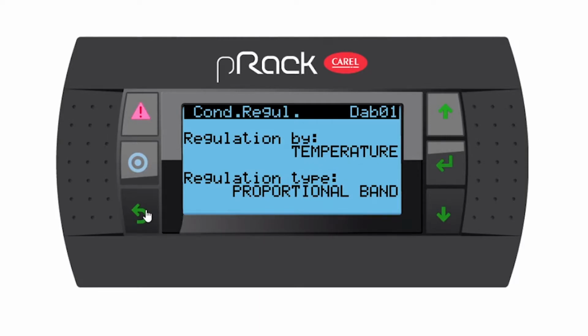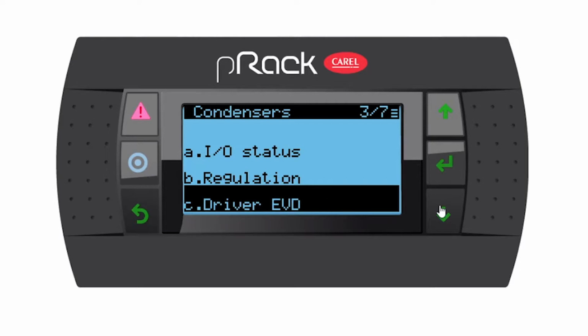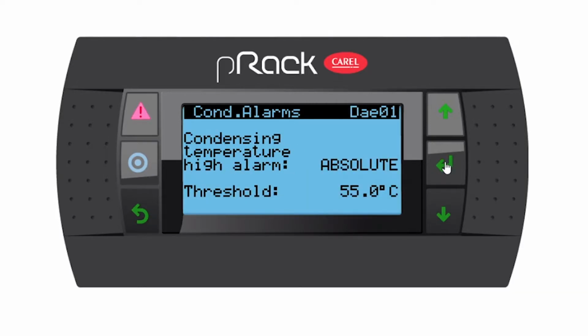So let's escape from this menu and go down to menu E, alarms, and enter. Condensing temperature high alarm, absolute with a threshold. I'm going to leave it on absolute, but I'm going to change my threshold a little bit. So let's say 45 degrees should be fine enough for me. Perfect. If we go down, you have an alarm differential of 5 and a delay of 60 seconds. That's perfect. Let's go down.